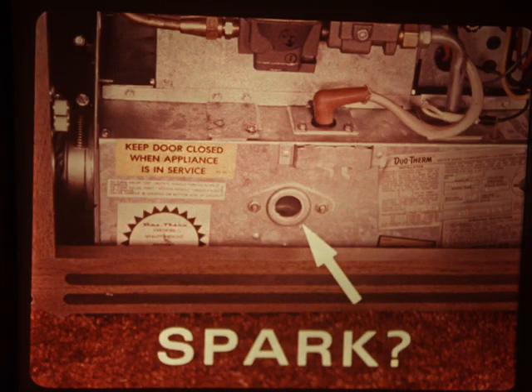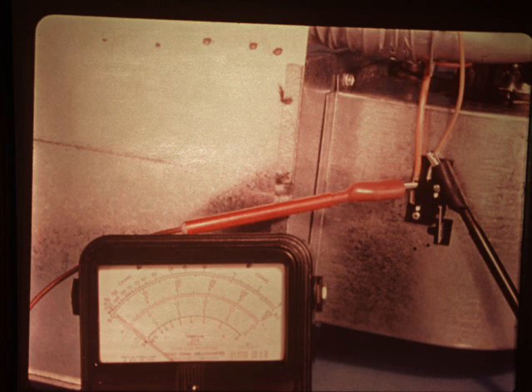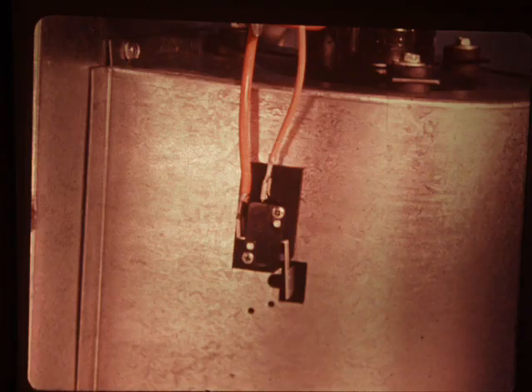If the blower operates properly, the next question is whether or not there's a spark at the igniter during startup. You should see a bright, continuous spark through the sight glass. If there's no spark, check for voltage through the sail switch circuit to the control module during the startup cycle. If there's no voltage, look for a faulty sail switch. Keep in mind that the blower must generate sufficient airflow to close the switch. Look for obstructions to the airflow that might keep the switch from closing.